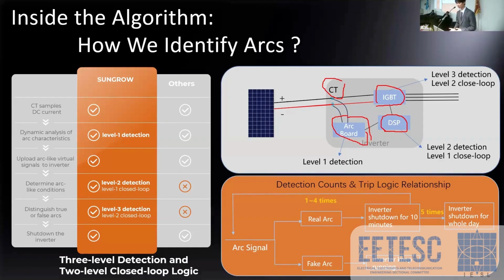And then we go to level two, because sometimes the inverter will make its own noise. So level 2 will decide whether this noise comes from inside or it's a true arc fault. If it still cannot be determined at level 2, then we go to level 3, where the IGBT will do a suicide trial to cut off the current instantly. Then if the arc comes again, that's a real arc. If it just dies, because when you cut the current the intensive flow of energy just stops, it just dies like this. So that's the 3-level detection.